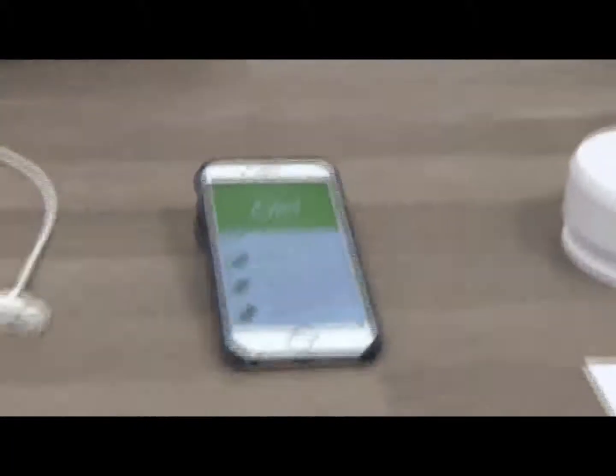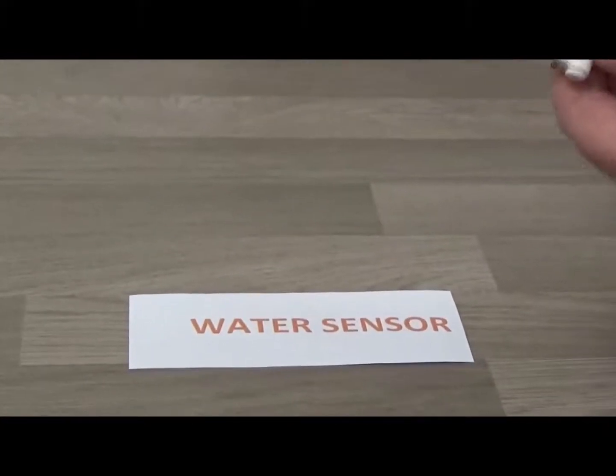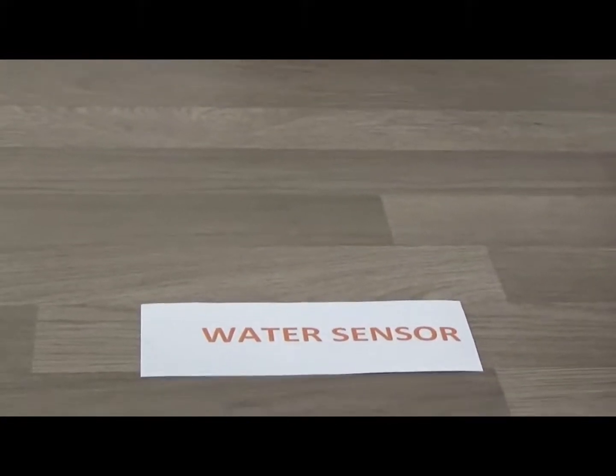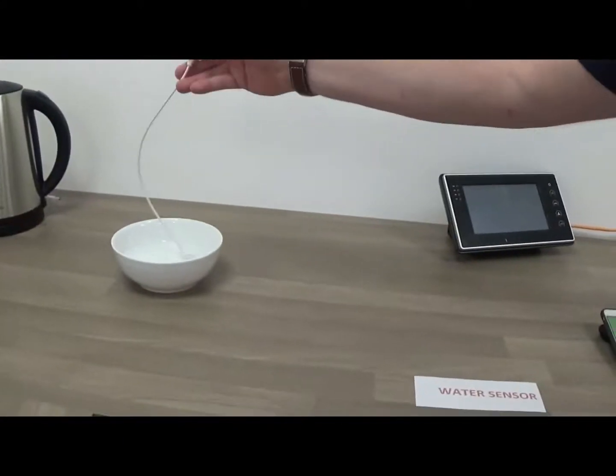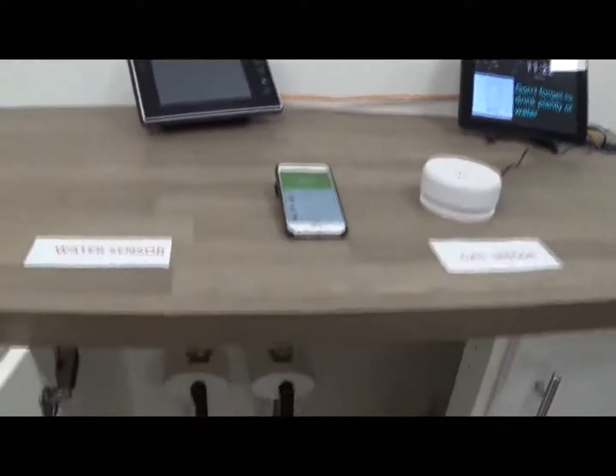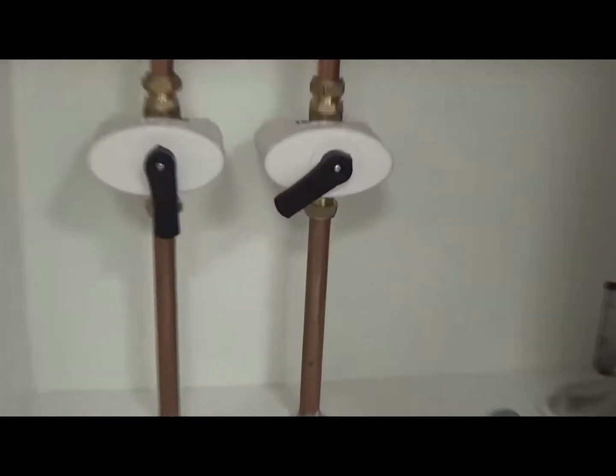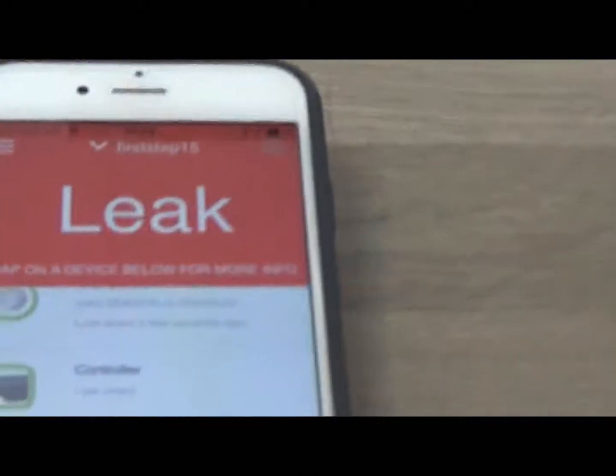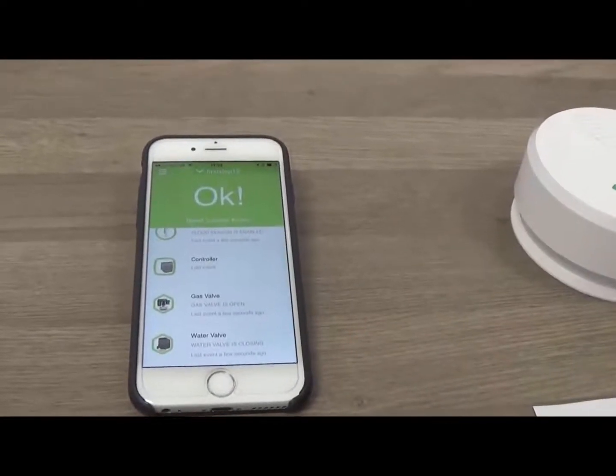The other element is to show how a flood could be identified. Here we have a flood sensor with a wall-mounting unit and the actual sensor itself. We'll just drop in some water — you get an audible alert confirming it's been detected. Immediately, the water isolation valve is moving to a closed position, and looking at the application it is now saying we have a leak on the system.